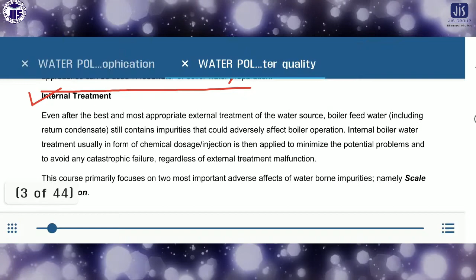Is there any chance that by this process we can treat the water internally? Okay, there may be. So what is the internal treatment? In the case of internal treatment, look here: even after the best and most appropriate external treatment of the water source, boiler feed water including return condensate, both cases, the raw water and the condensed water, both still contain impurities that could adversely affect the boiler operation.